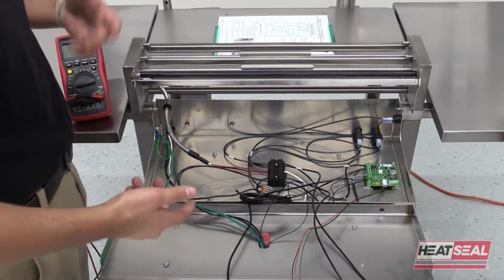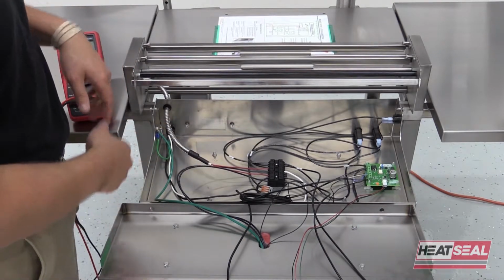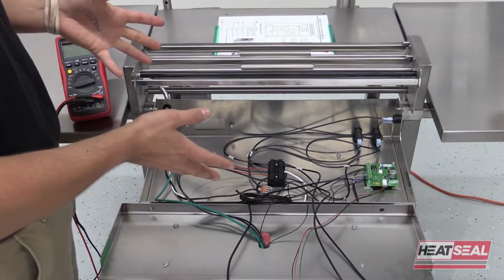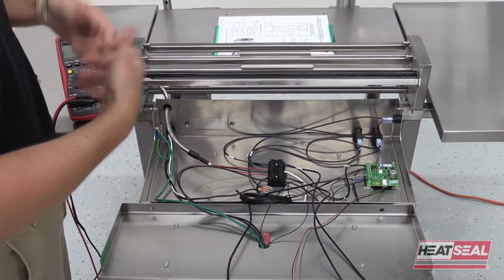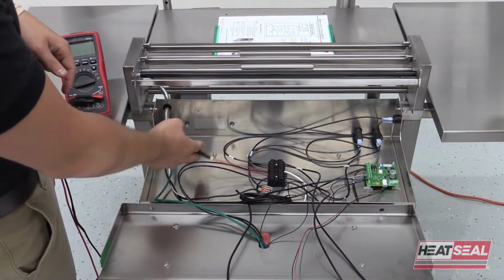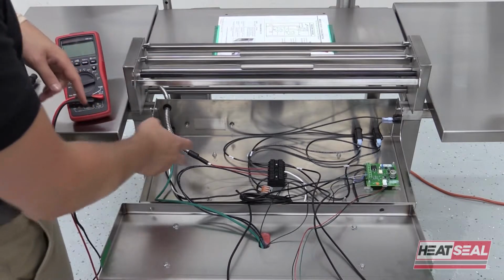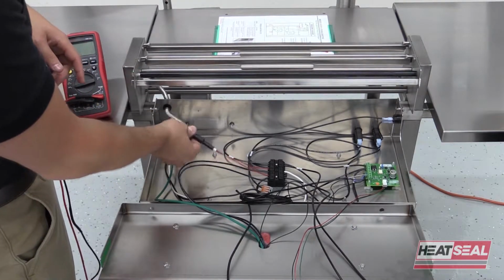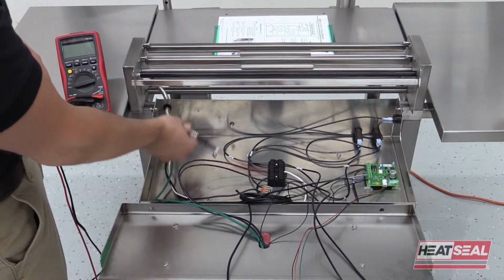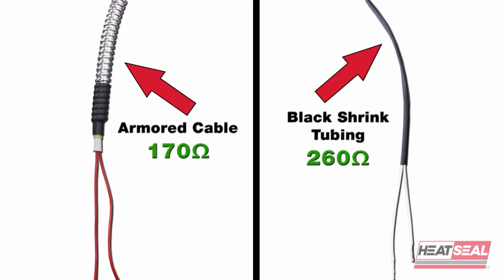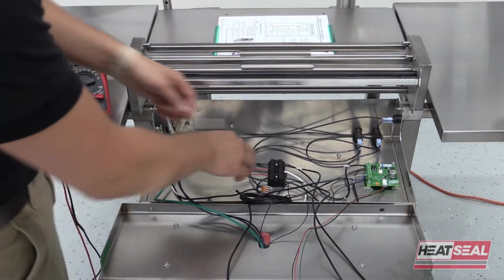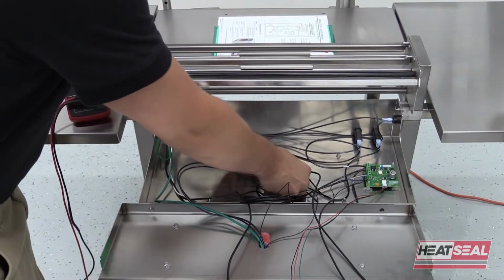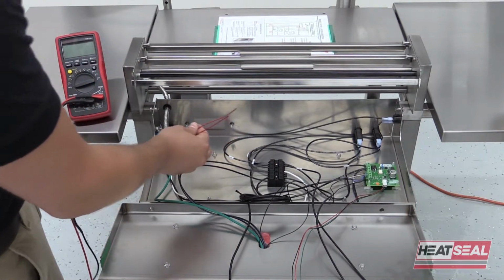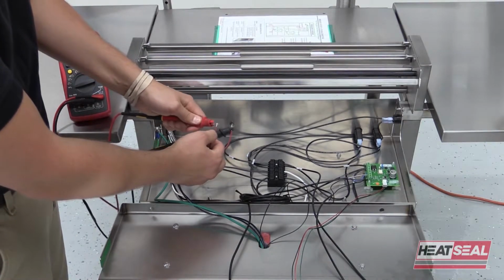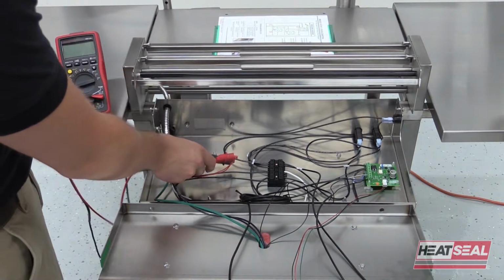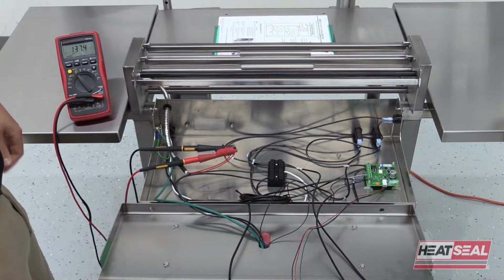Okay, so if your hot rod is not working and your 1 amp circuit breaker is not tripped, what you'll want to do is disconnect the hot rod with the power off and the machine unplugged, and we're going to check the resistance of the hot rod itself. We have two different kinds of hot rods depending on when your machine was manufactured. You'll have one that has armored cable that looks like this, and another kind that's just black shrink tubing. So what you'll want to do is push down on these terminal block tabs to disconnect the hot rod. We're going to connect to each side, and then we're going to switch this over to read ohms.